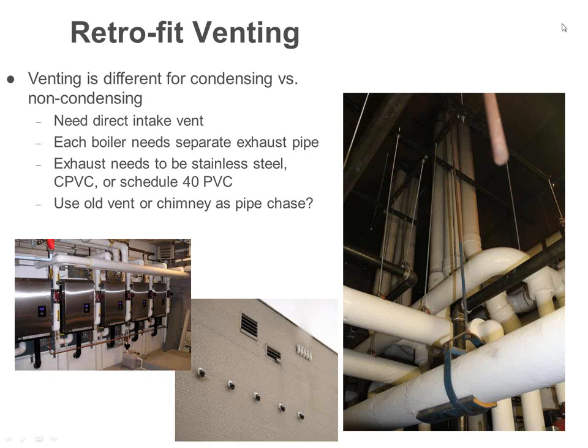You can't just dump it up the old flue, okay, because your flue will basically be raining, and within a matter of years that chimney will be on the ground. Okay, so venting is very critical. You have to follow what the manufacturer says as far as lengths, because these are basically a power burner type situation. Right? So there are limits to how far you can push that flue gas.